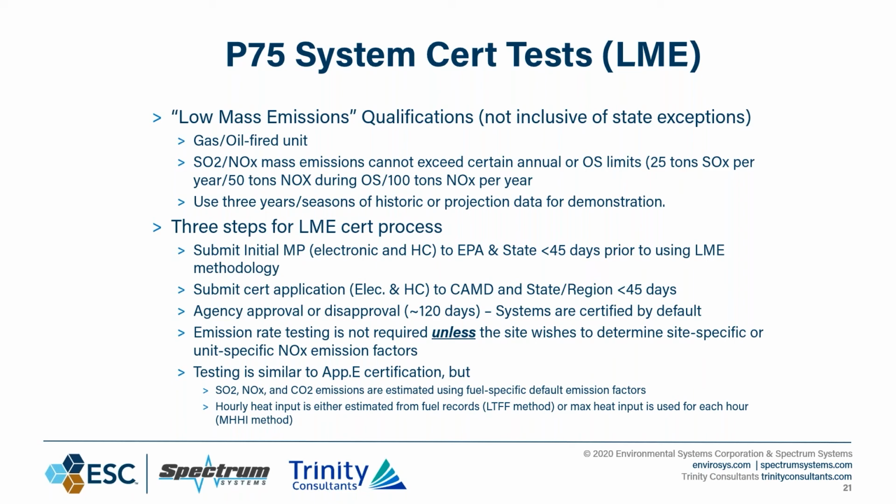And your hourly heat input can be either estimated from your fuel records using a long-term fuel flow method over the course of operation, or a maximum heat input value is used for each hour.